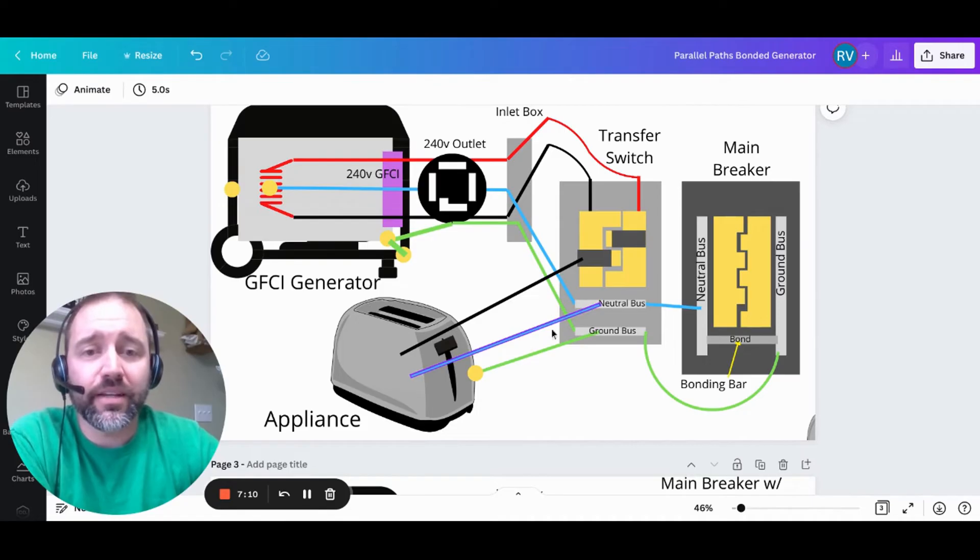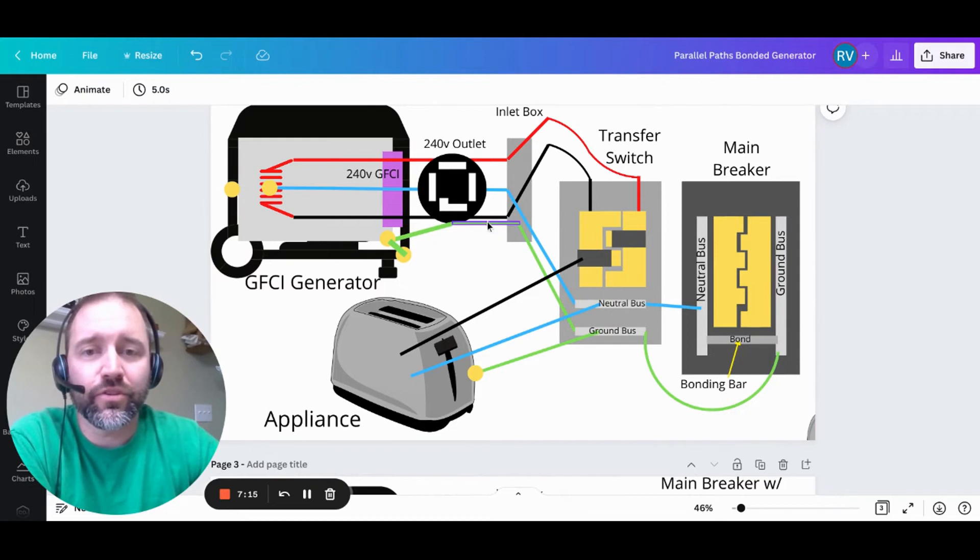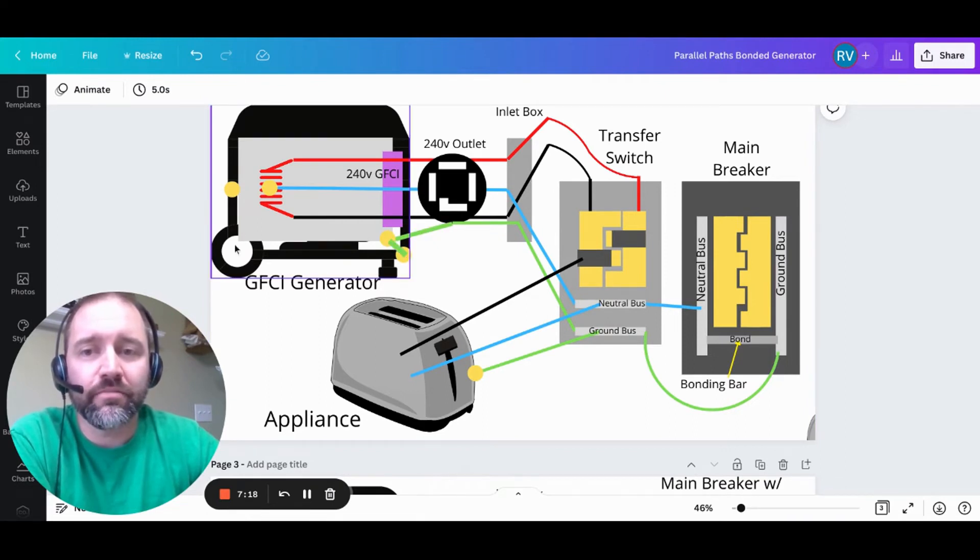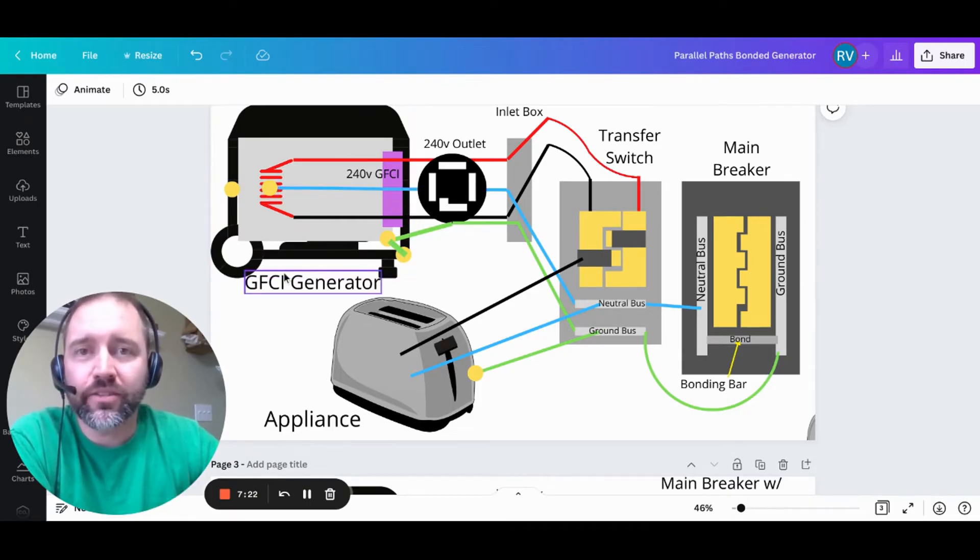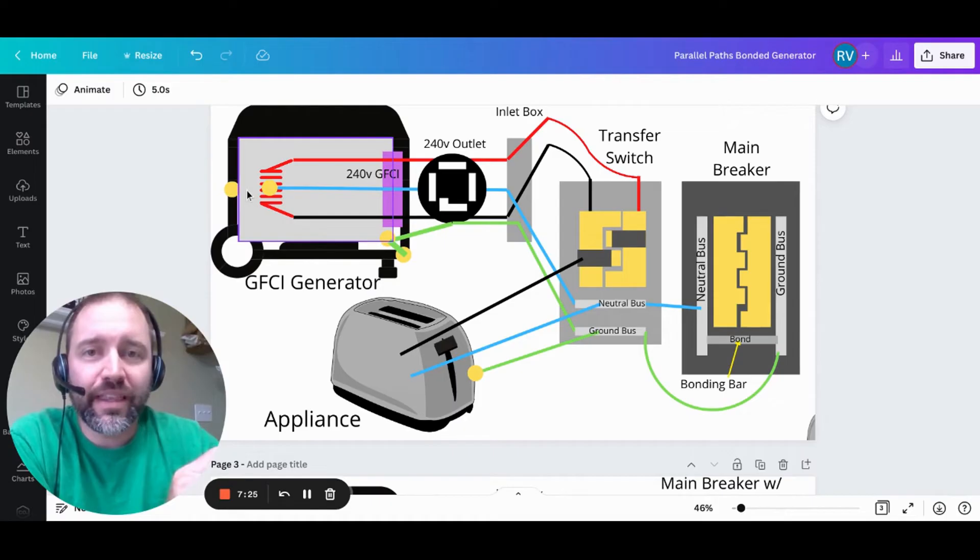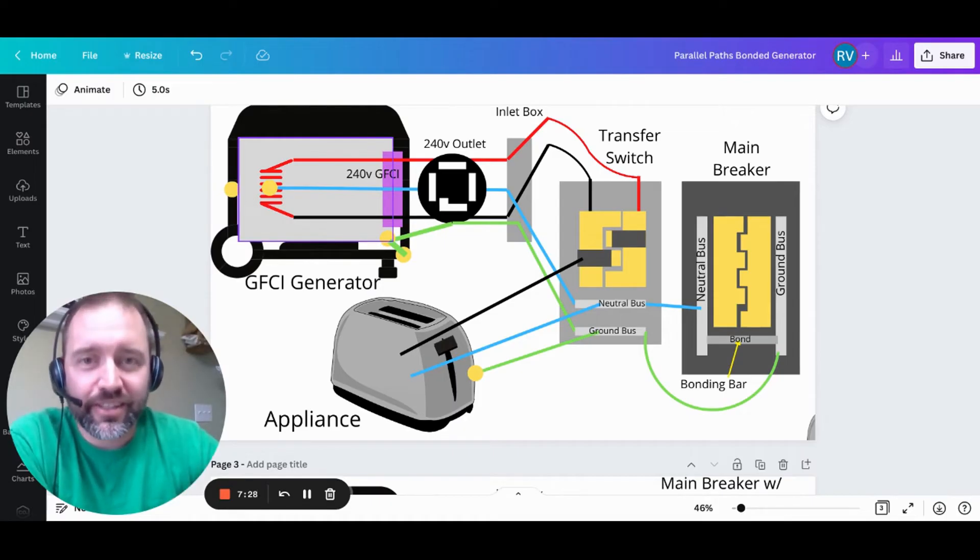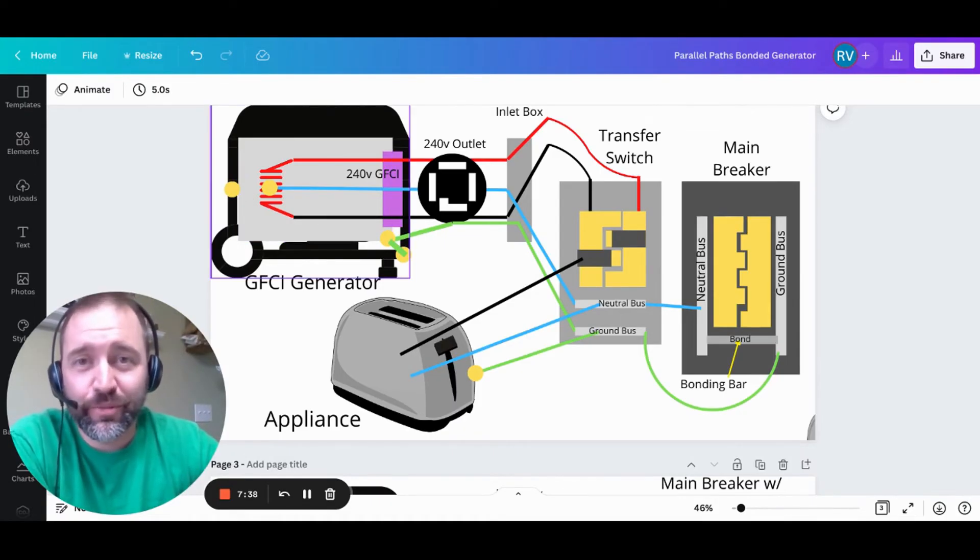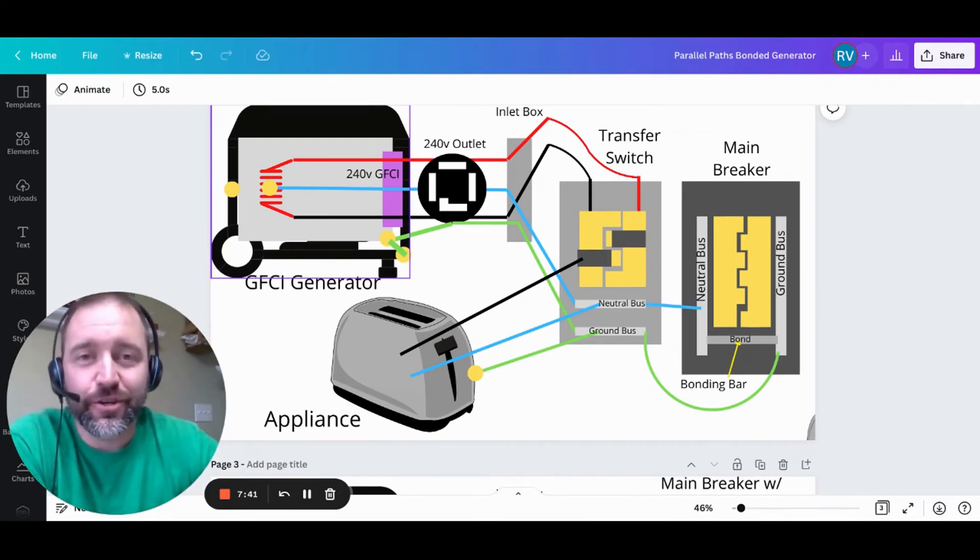And that's because when it hits this neutral bus, it's not going to jump over and across because there's no path back to the source. It can't attach back to the neutral here. There's no bond, so everything's going to be good to go. So just by removing that bond, more than likely, your generator is going to stay on and function as it should, assuming that was your problem, which in many cases, that is the issue.